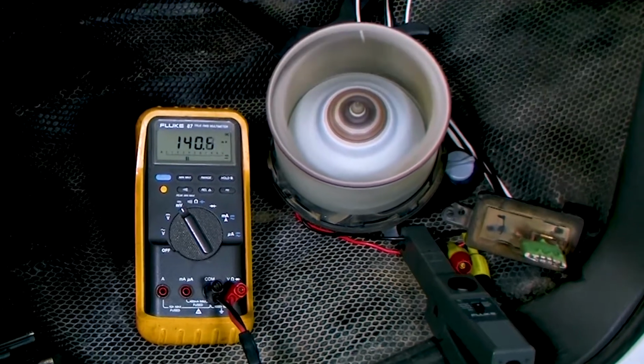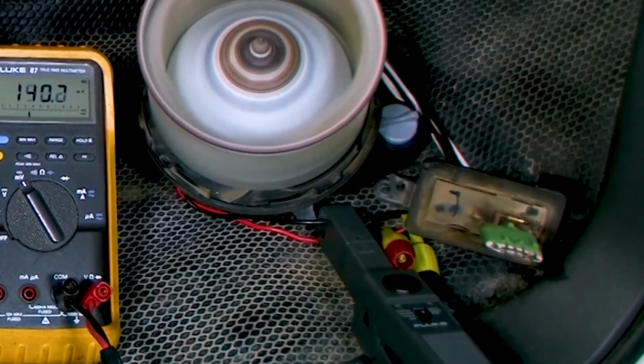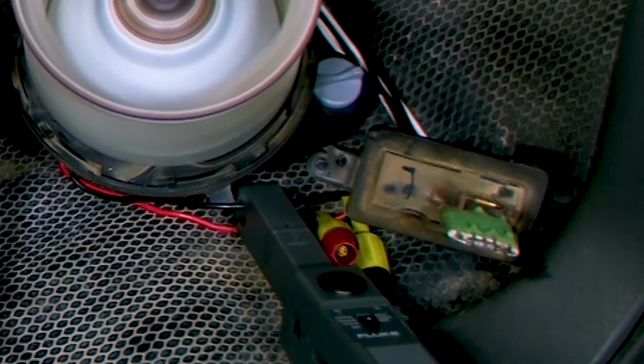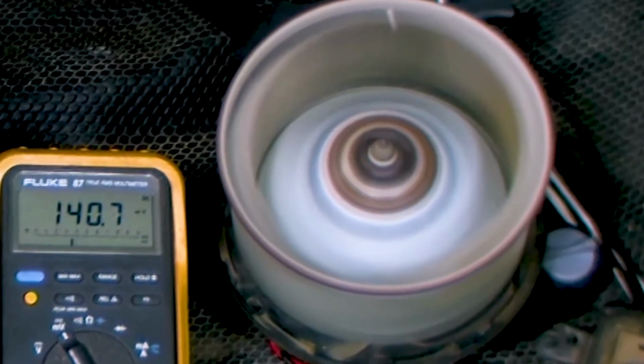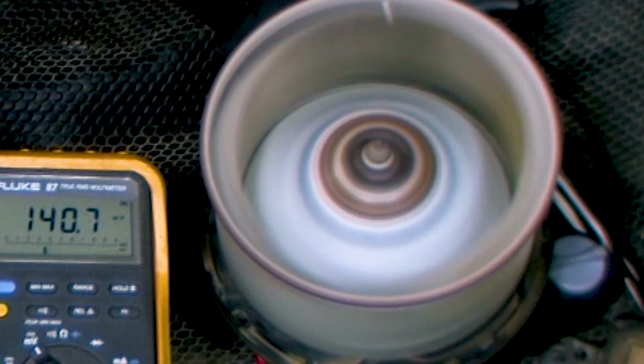The problem, of course, is that the failed resistor is frequently replaced by itself, when in fact the root cause of the failure is the aging, failing blower motor. Inevitably, the new resistor fails prematurely because the faulty motor was not identified and replaced.